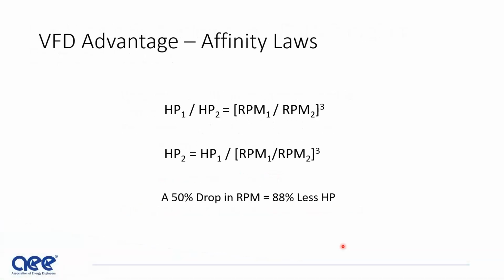So VFD basics. The whole idea of VFDs is based on the affinity laws. Here you see a simple representation of the affinity laws. You have your original horsepower, and then your new realized horsepower is equal to the ratio of the original RPM and the new RPM cubed. So if we solve for the realized horsepower, it's going to be equal to the original horsepower divided by this ratio cubed. So a 50% drop in RPM is going to create 87% less horsepower.